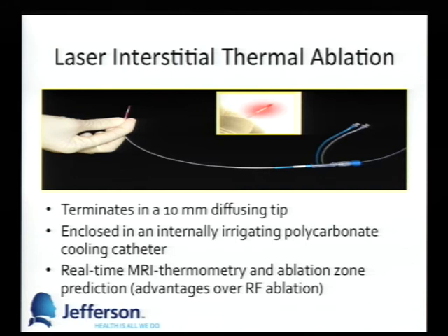So this is what the fiber optic tool looks like. We'll show you later. Once the anchor bolt is actually inside the skull, and I'll talk you through that, we put this catheter piece. This is the probe that goes to the brain, and this is the fiber optic tool that's going to come outside the MRI suite into the machine. The machine that delivers the laser energy is not MRI compatible.